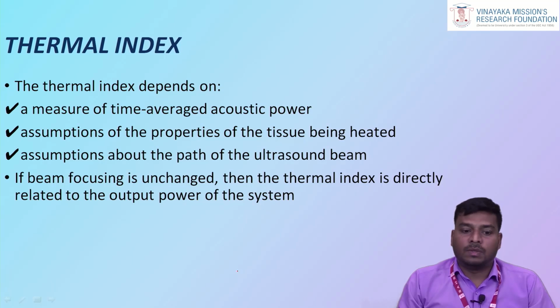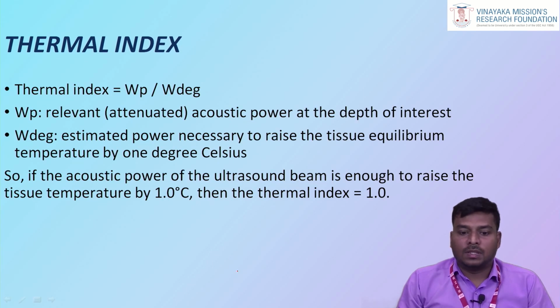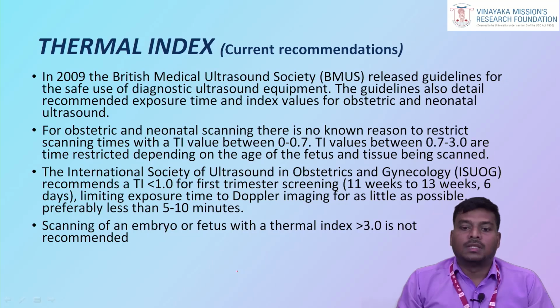Thermal index depends on three measures: a measure of time-averaged acoustic power, and an assumption of the properties of the tissue being heated. Heated here means heating from the sound energy. It also depends on an assumption about the path of the ultrasound beam. If beam focusing is unchanged, then the thermal index is directly related to the output power of the system. Thermal index is the relevant attenuated acoustic power at the depth of interest, relative to the estimated power necessary to raise tissue equilibrium temperature by 1 degree Celsius. So if the acoustic power of the ultrasound beam is enough to raise the tissue temperature by 1 degree, then the thermal index is 1.0.